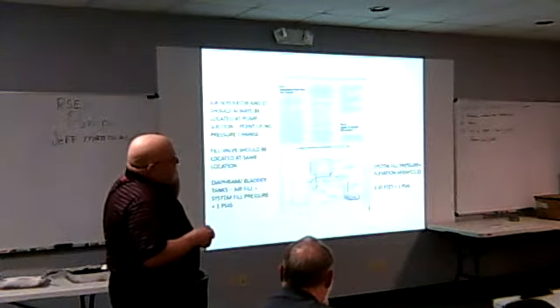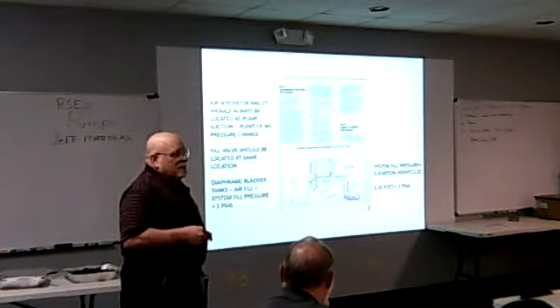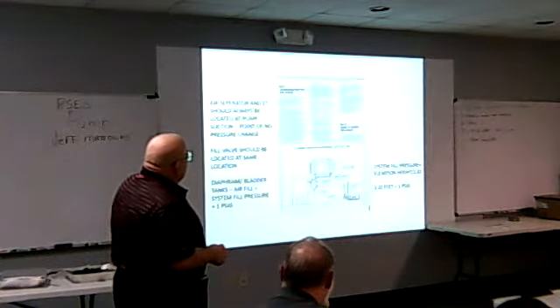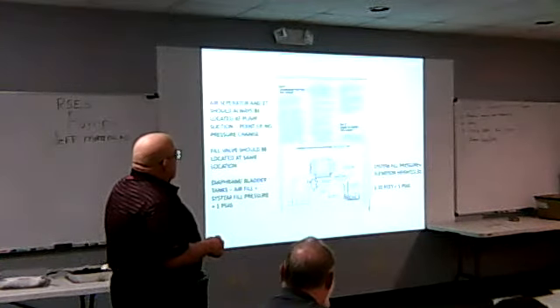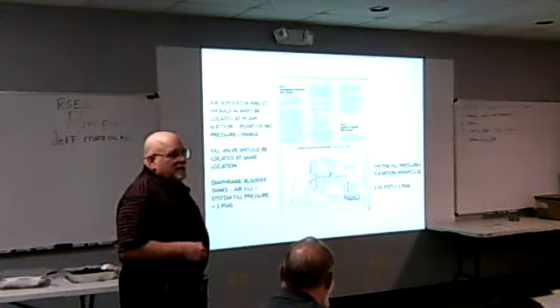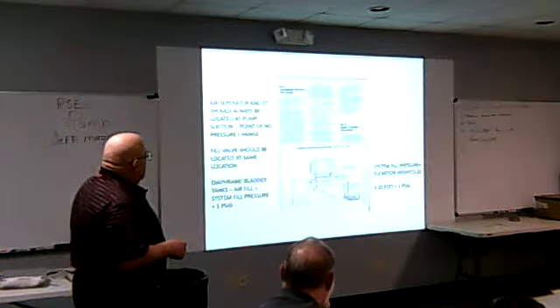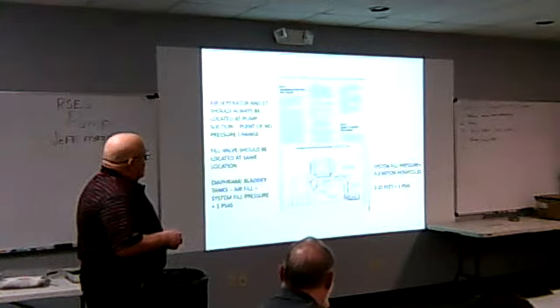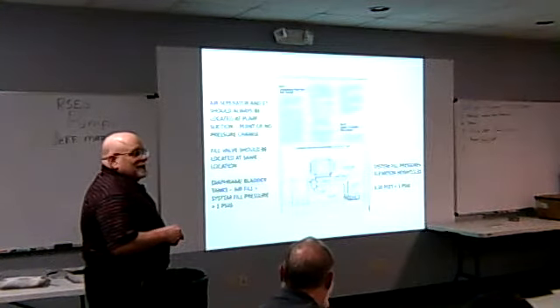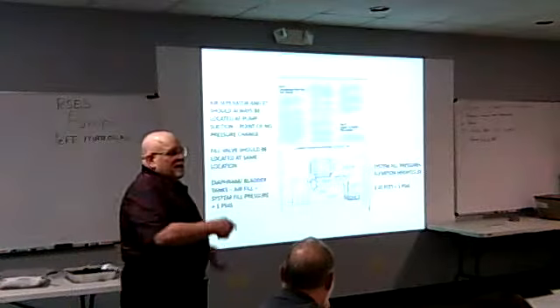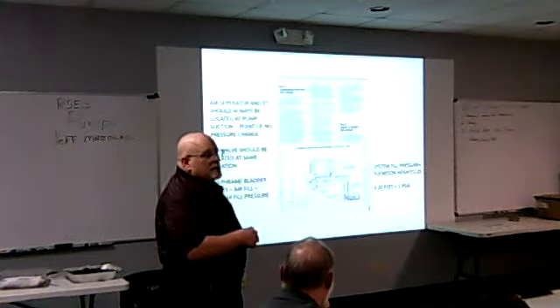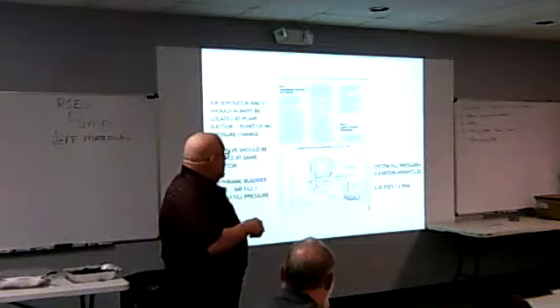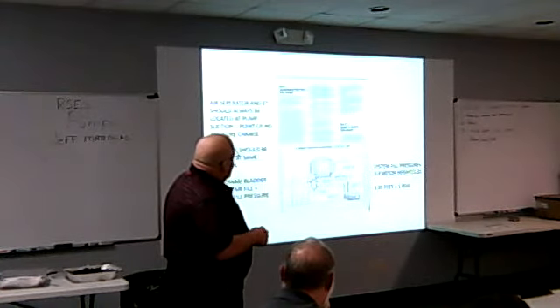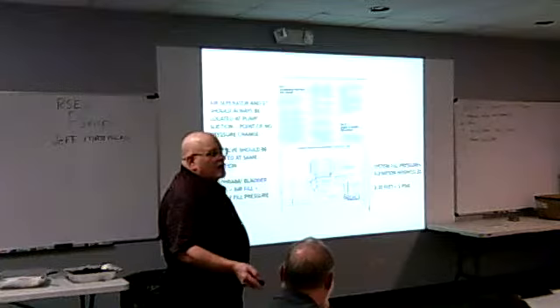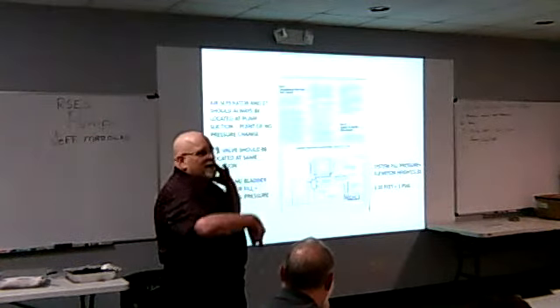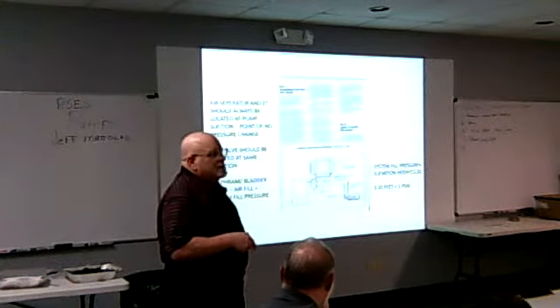Just a note, anytime you do an air separator, it always goes with the pump suction. We show it here. Here's your pump suction, this is your air separator. This is also where your expansion tank ties in. If you have a plain steel expansion tank, you want the air relief on the top of the tank to be piped back to the tank. Any air I remove from the system, I want to put back in my tank. I want to recover it. When I have a bladder type tank here, I want to put an air vent here, and vent the air off. I don't want it going to the bladder tank. I don't want air in that bladder. I want it on the outside, not on the inside. Okay.